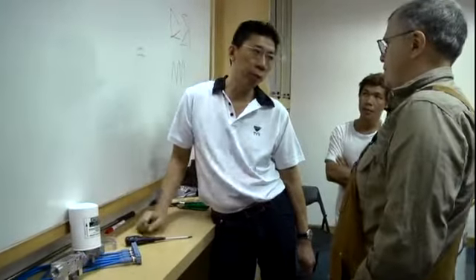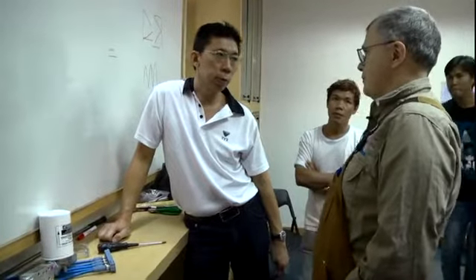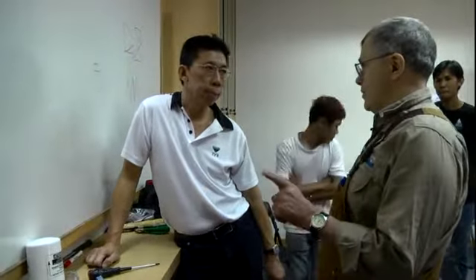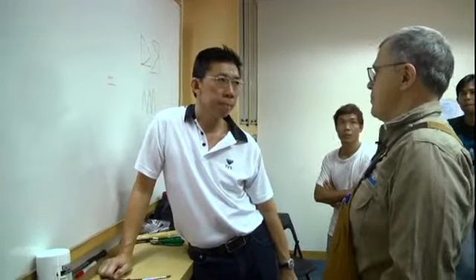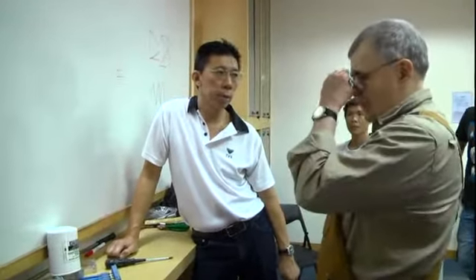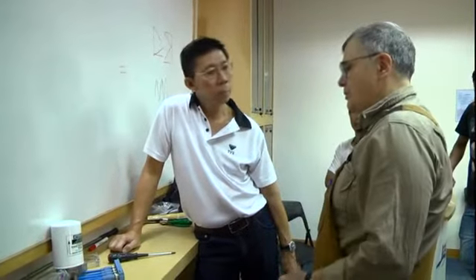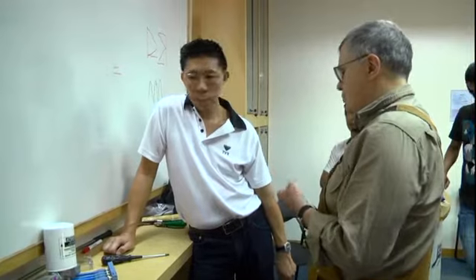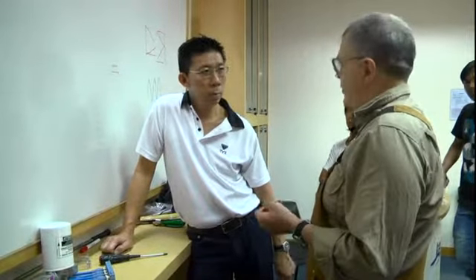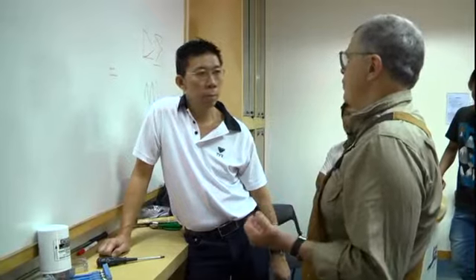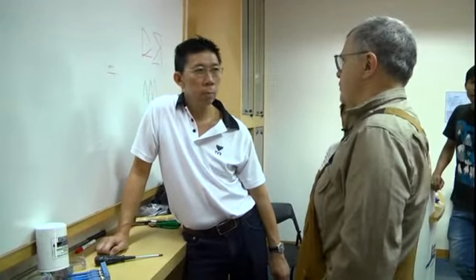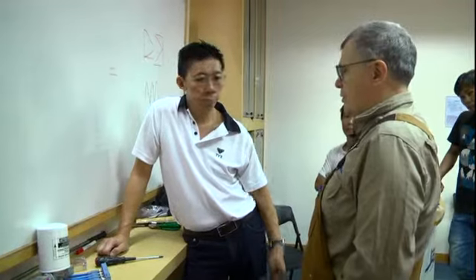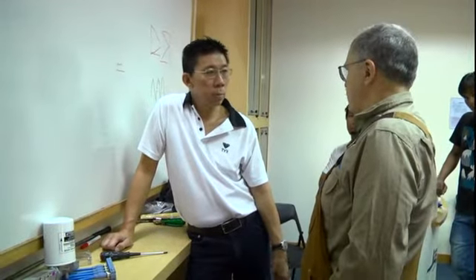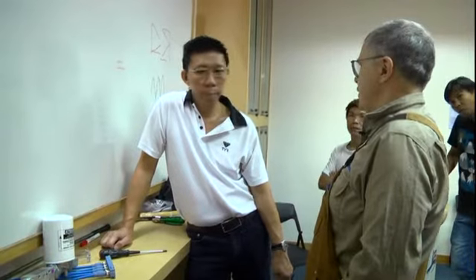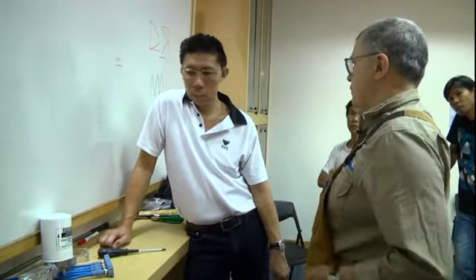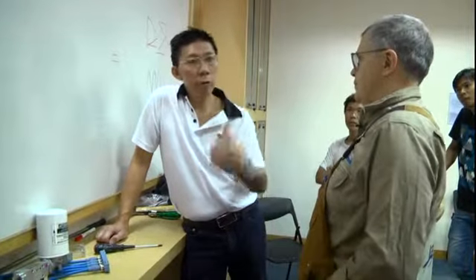Switches on the back of the meter. Dip switches or rotary switches? Dip switches. That was an analog meter, single needle in it. Right, that's our old Cruise Master system. Yes, Cruise Master. That is a little more difficult to calibrate. The last four switches, switches 6, 7, 8, and 9, do the idle consumption adjustment. Switches 1 through 5 are the totalizer calibration. Most of the ships you'll be dealing with will require temperature compensated systems, which won't use that gauge. It'll have to be either a digital gauge or the FloScan gauge. But most of the time we use the Cruise Master.